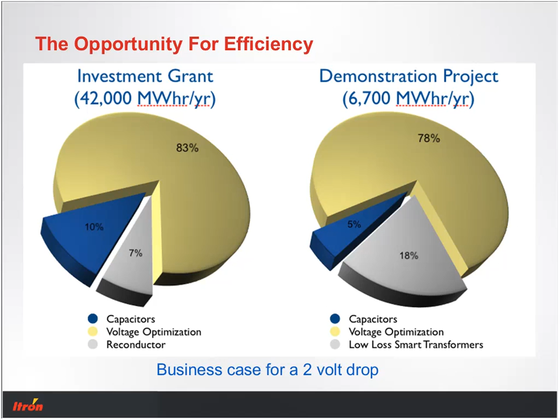So what are we really trying to achieve in a picture here? Well, voltage optimization, if we look at a normal feeder, we have a drop from the head end of the feeder to the opposite end of the feeder, where the last customer is served. And typically out of the substation, that voltage might be 126. So if you were one of the first houses out, you would be in that 126 volt range. If we go all the way out to the end of the feeder, it's going to be something less than that. In this case, somewhere around 117 volts. So that's a 9-volt drop from one end of the feeder to the other.